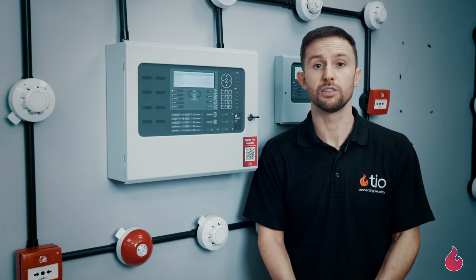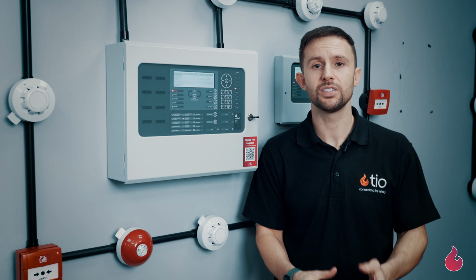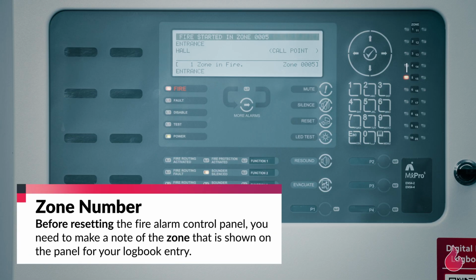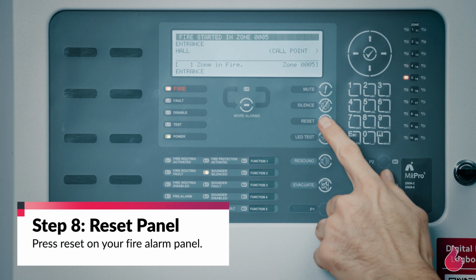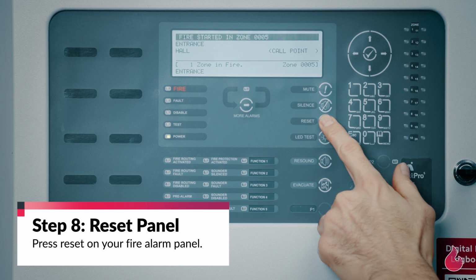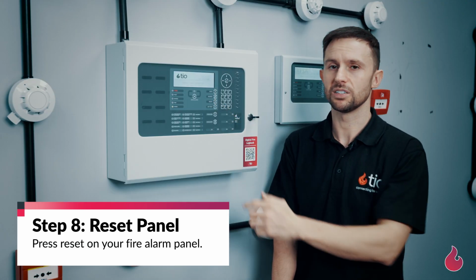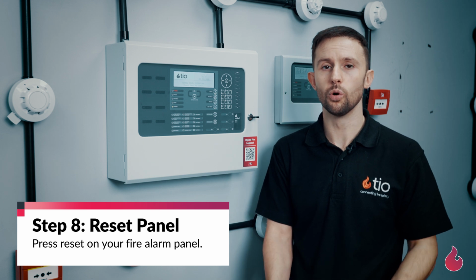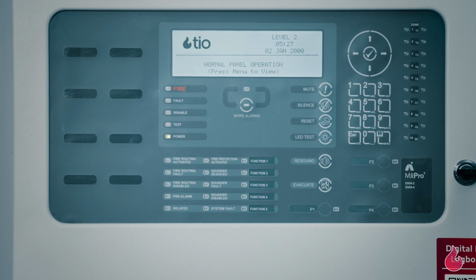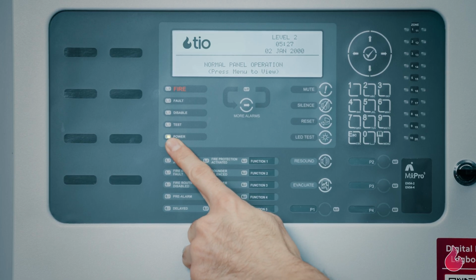Once we've successfully reset the call point, we can now reset the fire alarm panel. I can now press reset on my fire alarm system. After about 10 to 15 seconds, the fire alarm panel should go back to a normal condition, and the only LED that it should be showing is the green power LED right here.